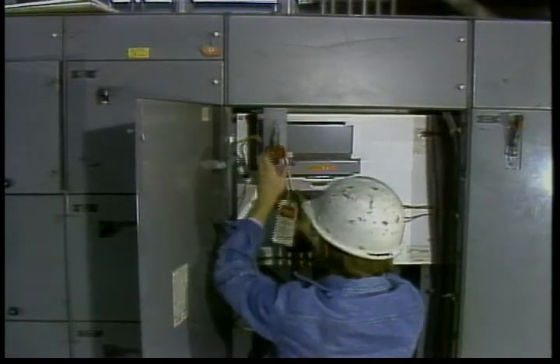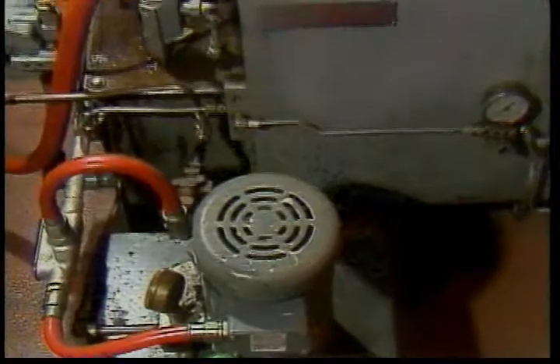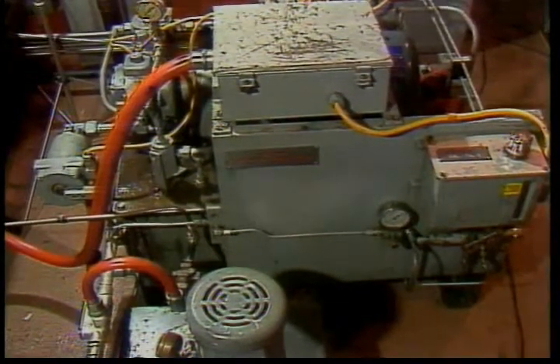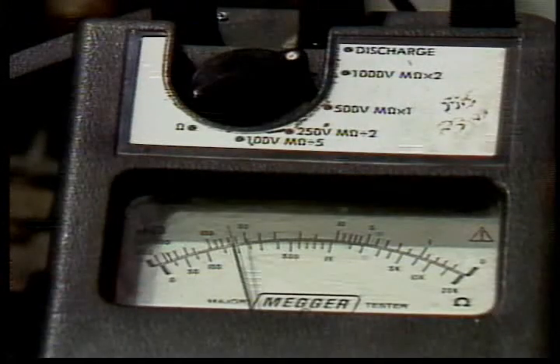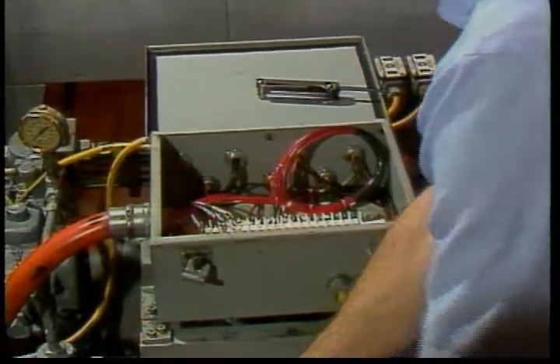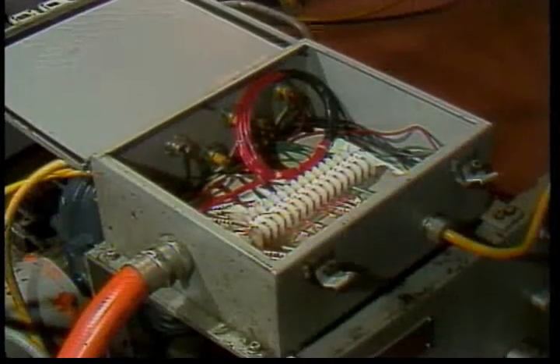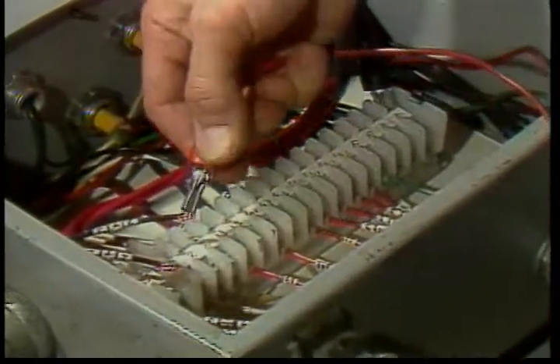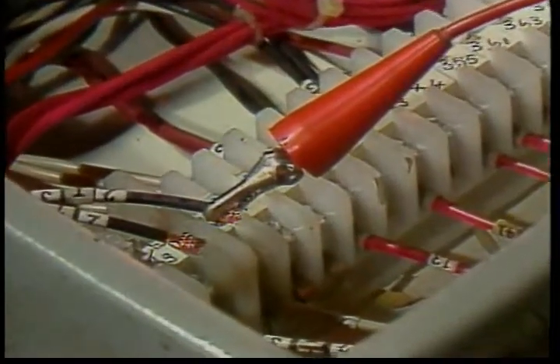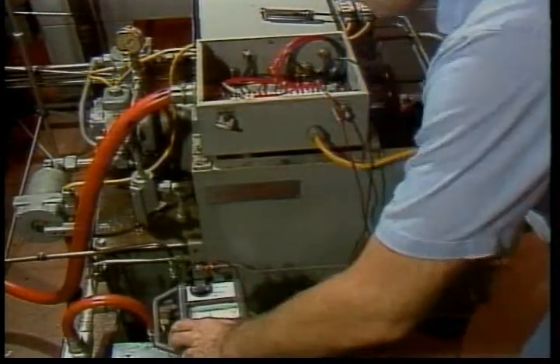Other motor problems may not be so obvious. To find them before they damage the motor takes instruments and careful record keeping. In many plants, the insulation inside a motor is periodically checked with a megohmmeter. Unlike a standard ohmmeter which uses a small battery, a megohmmeter uses a high voltage equal to or greater than normal power line voltage. This allows it to measure very high resistances accurately and puts the insulation under high voltage stress so defects are more likely to show up.